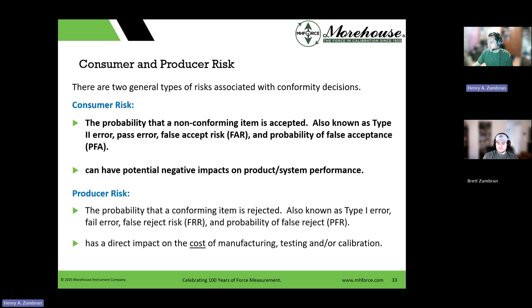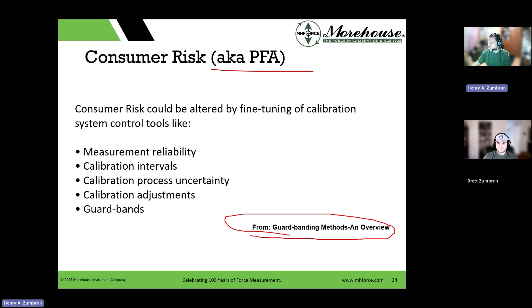If we want to fine tune our PFA, we can do things like measurement reliability. We can look at our calibration intervals. We can buy better standards, lower our process measurement uncertainty, and make calibration adjustments. If it's too close, maybe we have some run rules. We can implement guard bands. This is all from the paper Guard Band Methods and Overview. If you don't have it, go out and get it. It's quite an excellent paper.